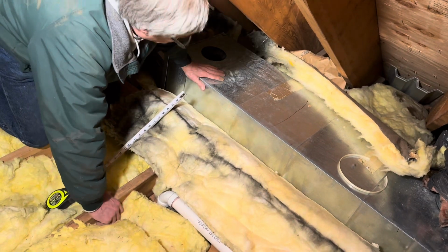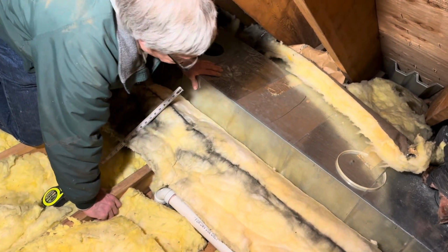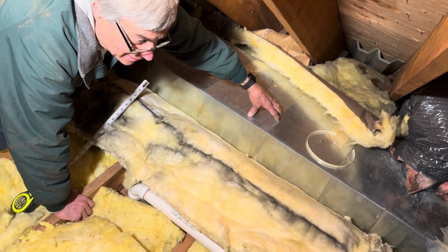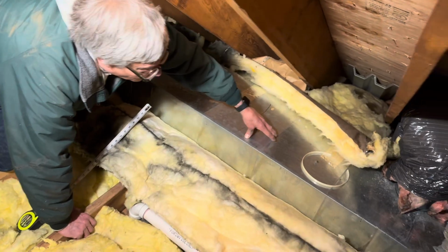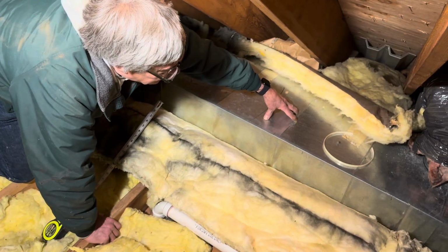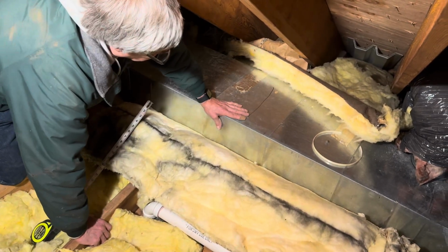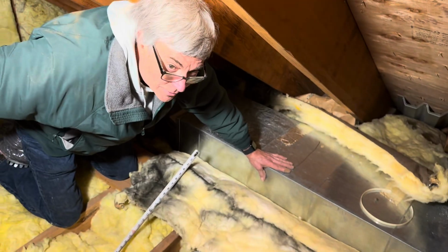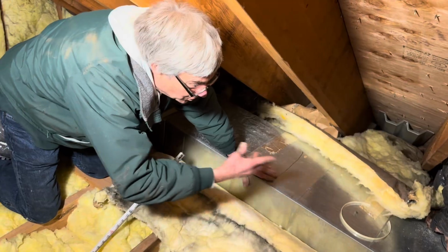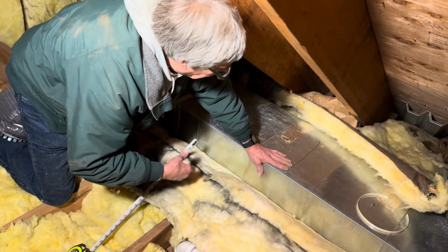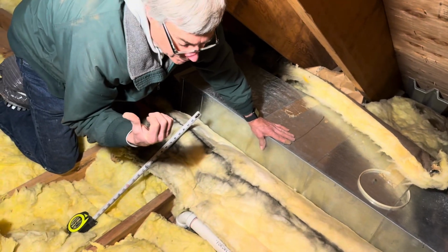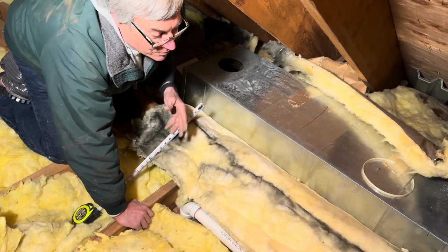And then because we have another duct that we're going to relocate and add to the system, because when we did our numbers, we found out that we actually have more air in this part of the trunk system than we need. So we're going to take that air and put it to a closer duct system, which will make this use up all the air that it's being distributed. And then this system will perform much better. That system will get more air to it, and the whole system will work and perform a lot better.